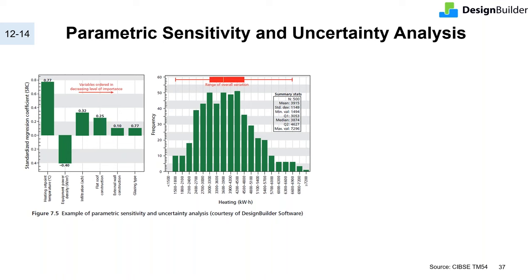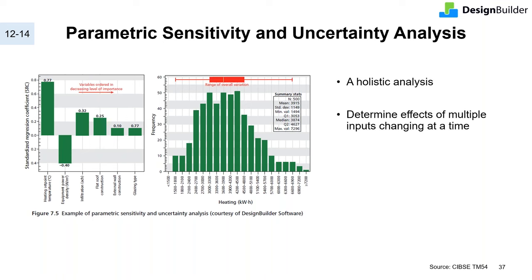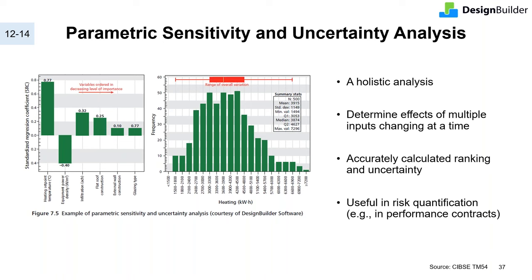A more structured way of assessing sensitivity is to do a multi-parameter analysis. This holistic analysis allows you to determine the combined effect of changing multiple inputs, because the combined effect may not be directly equivalent to the sum of its parts — some variables may cross-compensate each other. DesignBuilder can do these analyses in an automated way, and this module is fully integrated into the modeling interface. You can identify and rank design inputs in terms of importance. This parametric approach is especially useful in quantifying risk in projects procured under performance contracting where more accuracy is needed.